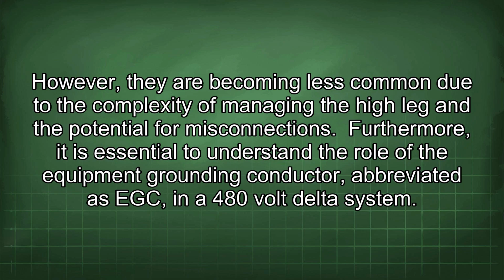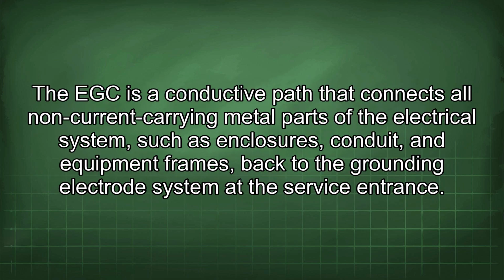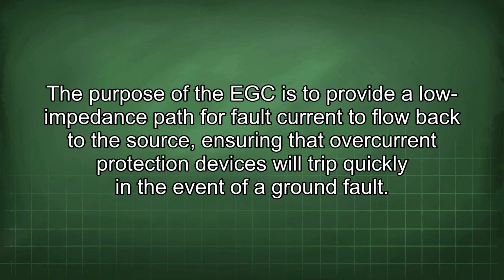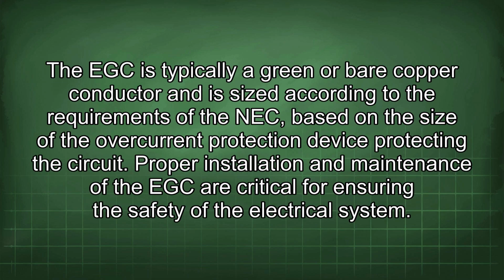Furthermore, it is essential to understand the role of the equipment grounding conductor, abbreviated as EGC, in a 480 volt delta system. The EGC is a conductive path that connects all non-current carrying metal parts of the electrical system, such as enclosures, conduit, and equipment frames, back to the grounding electrode system at the service entrance. The purpose of the EGC is to provide a low impedance path for fault current to flow back to the source, ensuring that overcurrent protection devices will trip quickly in the event of a ground fault. The EGC is typically a green or bare copper conductor and is sized according to the requirements of the NEC, based on the size of the overcurrent protection device protecting the circuit.